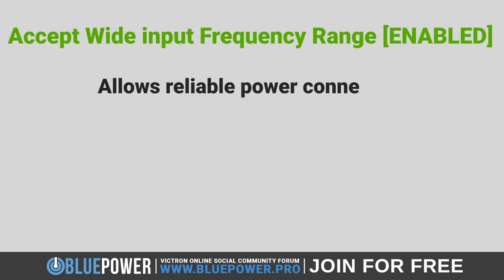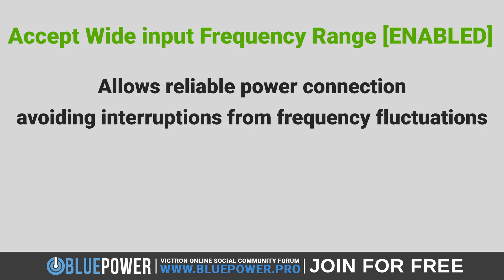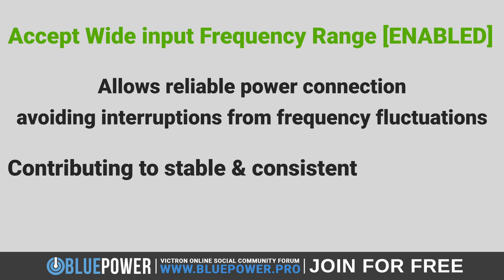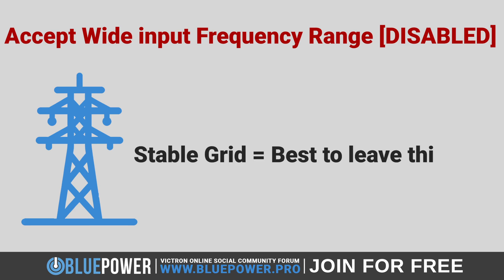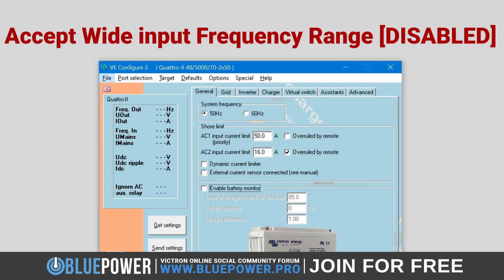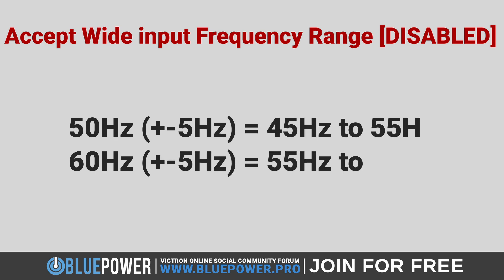It allows the inverter to remain connected to power sources, avoiding interruptions caused by minor frequency fluctuations, contributing to a more stable and consistent power supply. However, if you have a stable grid, then it's best to leave this off. Note that when the setting is disabled, the acceptable input frequency defaults to the system frequency value in the General tab, given a 5 Hz positive and negative leeway on each side.